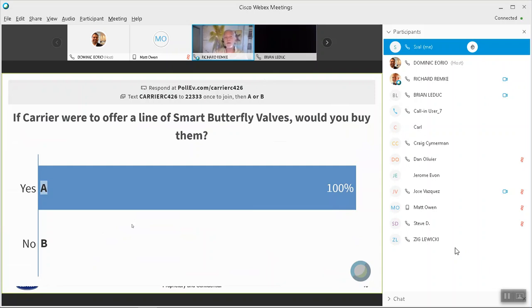It makes sense, obviously, for air handlers. We're looking at trying to bring in a line of smart valves that would cover those applications. But plants, where you would have up to 14-inch butterfly valves, that becomes an expensive endeavor to switch over to. From our perspective, we want to know if it's going to be worth the effort. Well, right now we've got 100% on that, and I'm going to keep moving because we do have some time constraints here.